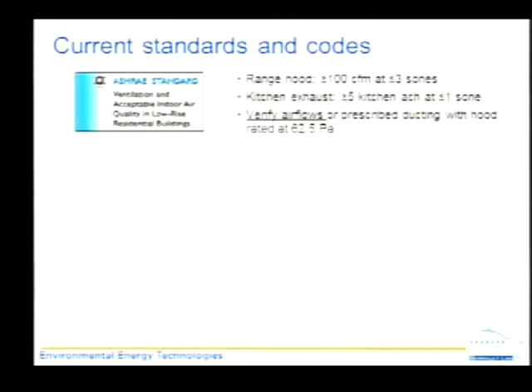Air changes per hour. Thank you. Excellent question. So this means that you set your flow rate according to the volume of the room that your kitchen is in. A very important part of this ASHRAE standard, it's very interesting too, because a lot of people know about ASHRAE ventilation standards, but they always think it's a general ventilation standard. There's a certain amount of air changes per hour required generally in your home, and they forget that there's this kitchen part, which is very important. There's also a bathroom part, which is very important. And those two parts may be even more important than the general.